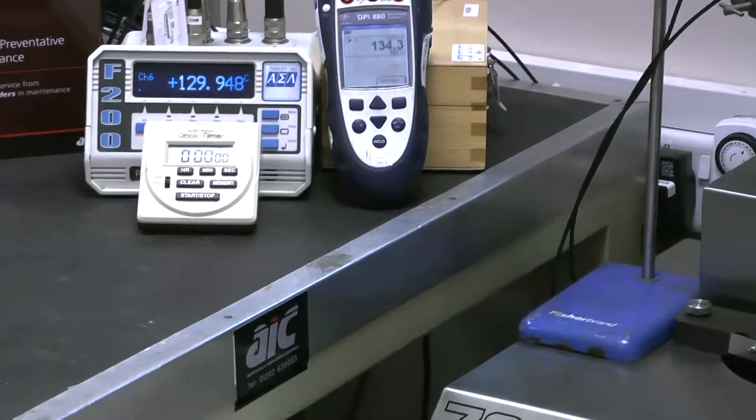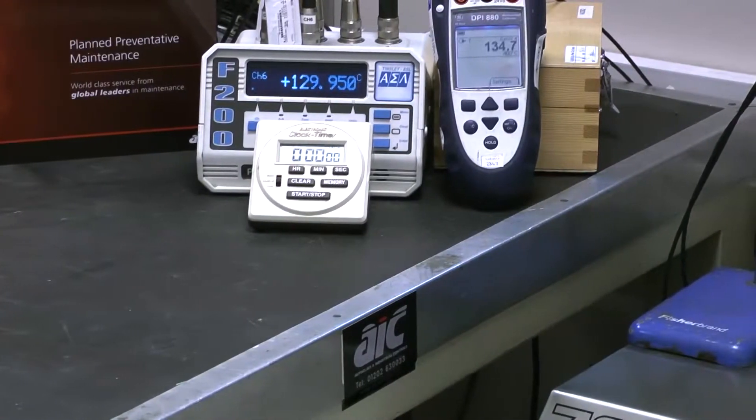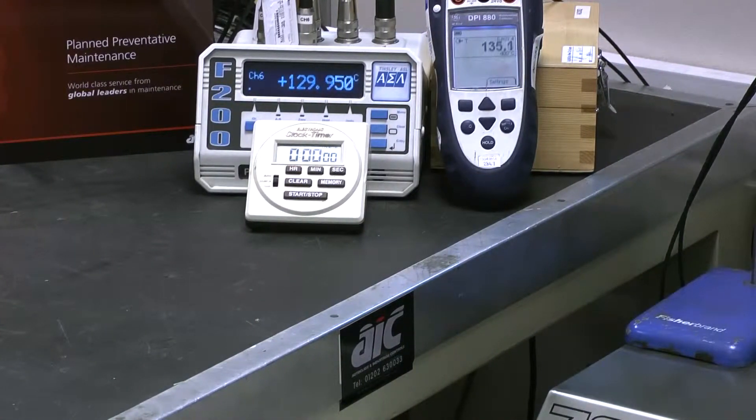If we look at the process calibrator, the reading on that is starting to go into quite a large error now. It's 135 degrees. And this will take a few minutes to stabilize.